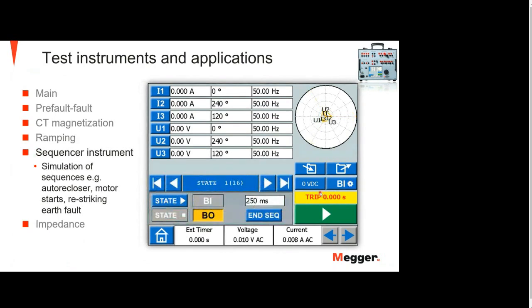So then we have the sequence instrument. The sequence instrument is like the pre-fault instrument, but in the pre-fault we have only 2 states, and in the sequencer instrument we have 16 states. When you have that many states, you could do simulations like testing an auto recloser, for example, or restriking a fault, or motor start, or this kind of thing. So it could be used when you need a lot of states to make a very long sequence.